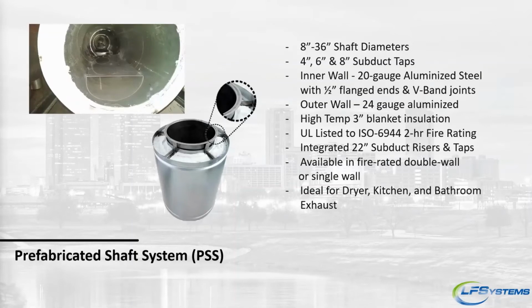And it doesn't even require a finish wall, though most people do box it in with single drywall. And this is ideal for everything we've talked about so far. So now, instead of having to worry about making sure that the subduct is 22 inches, making sure that the ductwork inside is smooth and free and clear, basically, you send this out to apprentices with a screwdriver and a caulk gun, and they can install it fairly quickly. It's a standard 1/2-inch flange, so many installers are familiar with that method of installation. It has a lot of benefits, one of them being space.